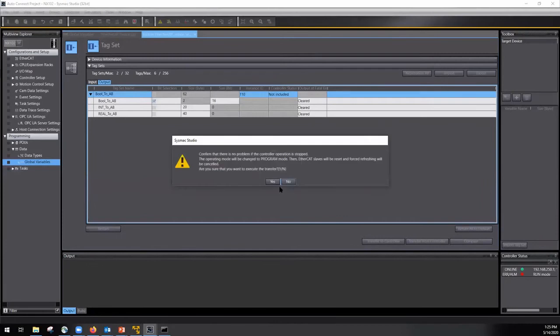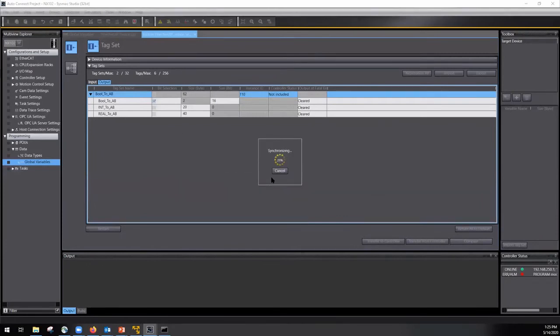Hey Stu, where did you get your input and output numbers on the Allen Bradley side? So 110 and 100? Those are my instance IDs that I set up in Sysmac. So I just made them 110 and 100. I could make them whatever I want as long as they match up on the Allen Bradley side or whatever other PLC you're pulling this with.